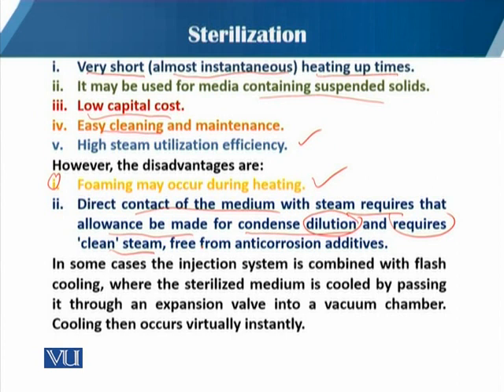The steam should be free from anti-corrosion additives. In some cases, the injector system is combined with flash cooling, where the sterilized medium is cooled by passing it through an expansion valve into a vacuum chamber, and cooling then occurs virtually instantly.